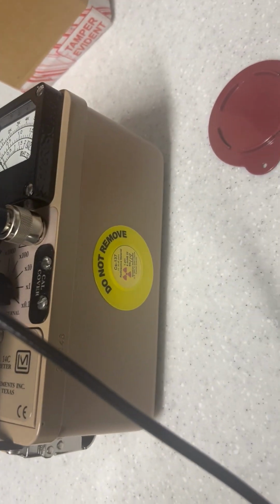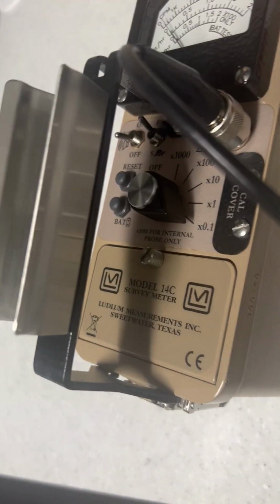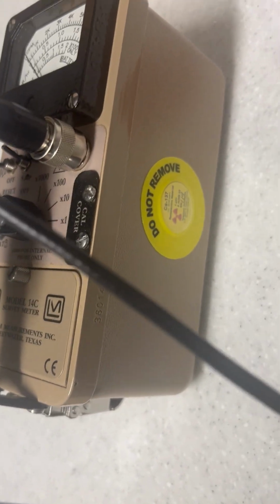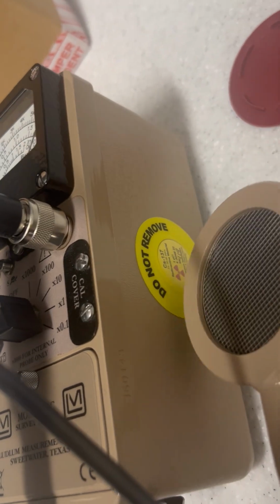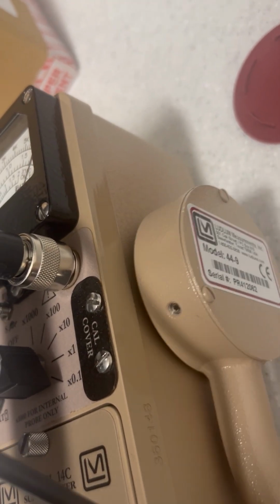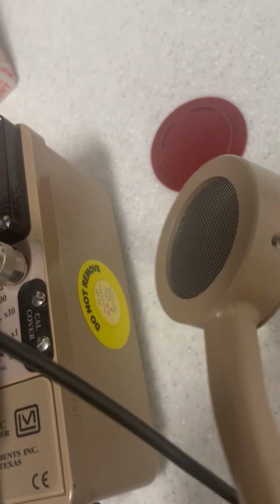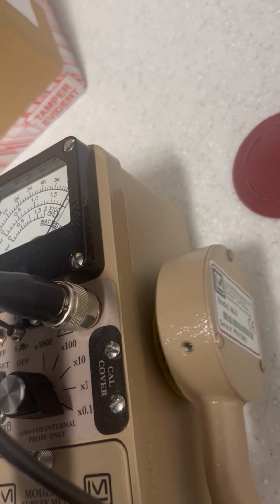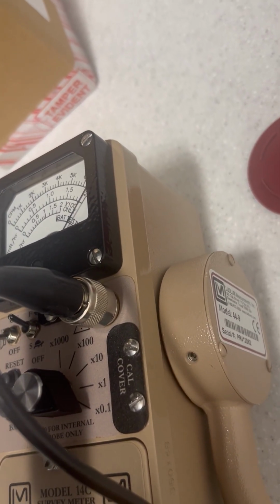So now over here to do the QC, you want to take it starting on its lowest setting, and you're going to put the window. You typically don't want to touch the source or touch anything on this thin window because that can damage it. Once it's damaged, the gas could leak out or it just won't be able to read.